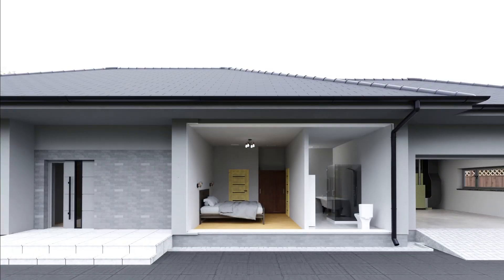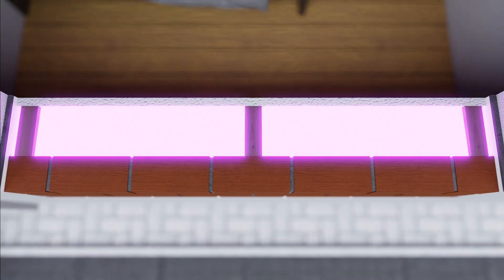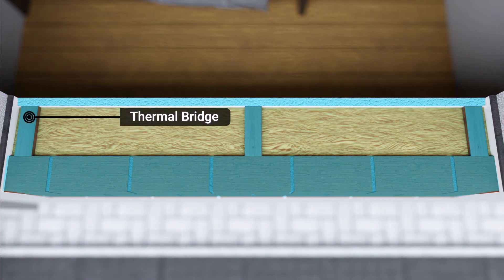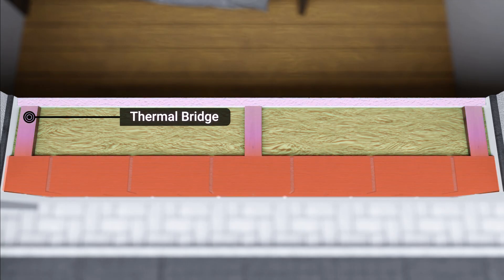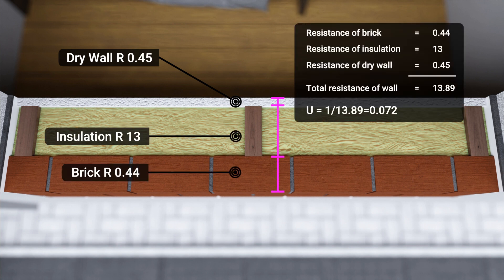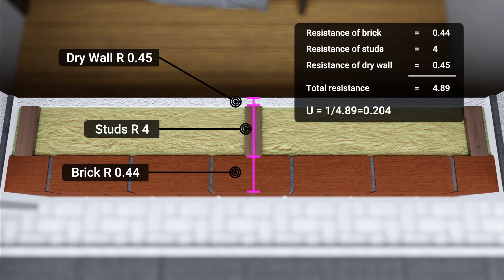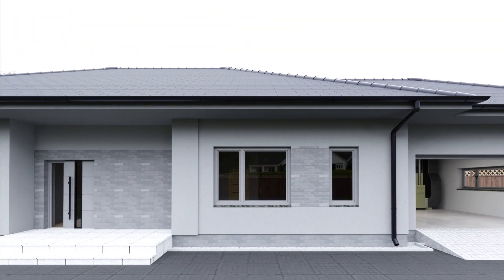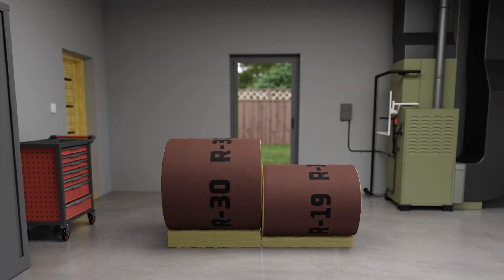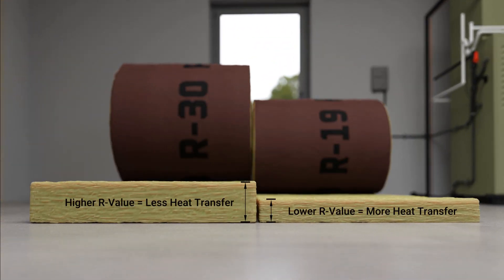It's important to be detailed when considering walls. Understanding the R-value of insulation is important, but the building materials in the wall also have R-values that need to be accounted for. We can control the wall thickness and insulation to minimize conduction. Manual J requires us to know the wall's R-value, which gives us an idea of how much the wall will resist conduction. Different materials, or similar materials of varying thicknesses, will have different R-values. A higher R-value indicates that material resists conduction well, and a lower R-value indicates the material isn't as effective at resisting conduction.